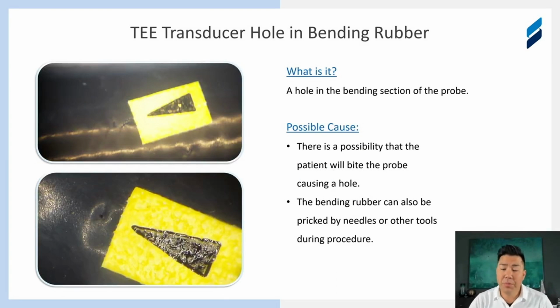Here we have a couple of very close-up pictures of some punctures in the bending rubber of a TEE probe. Pretty common. The bending rubber, again, is the section from here below the tip to the insertion tube. What that allows the probe to do is move in any direction for a user to manipulate the probe to get a perfect image of the heart.